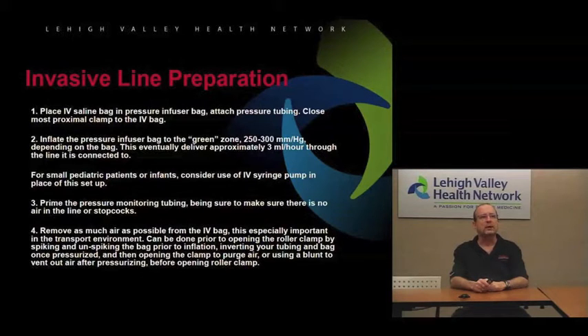To start with, and hopefully I'll have a video to go along with this off of YouTube or something along those lines, we'll place the IV saline bag in a pressure infuser bag, attach the pressure tubing, close the most proximal clamp to the IV bag, inflate the pressure infuser bag to the green zone, which would actually be about 250 to 300 millimeters of mercury on the gauge that's on the bag. It depends a little bit on the brand of the bag. And this will deliver approximately 3 milliliters an hour through the line it is connected to when everything's opened up.